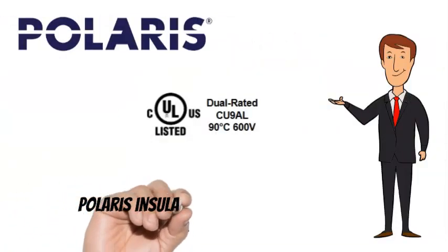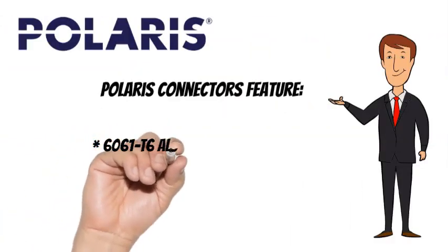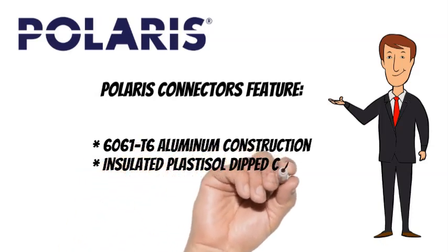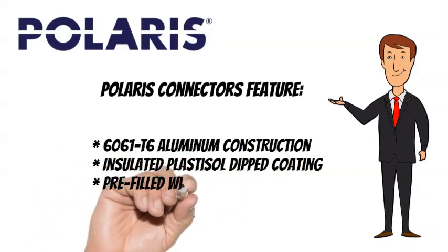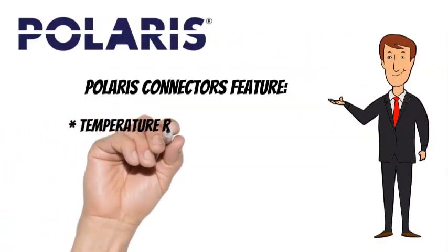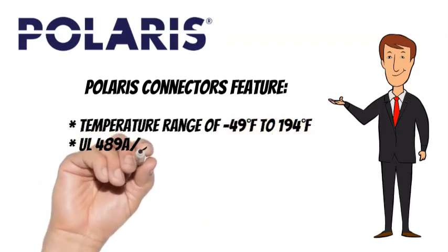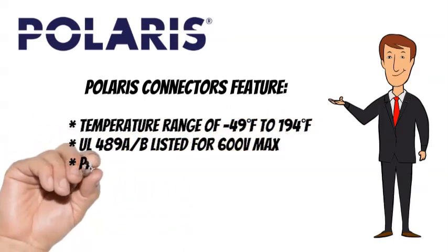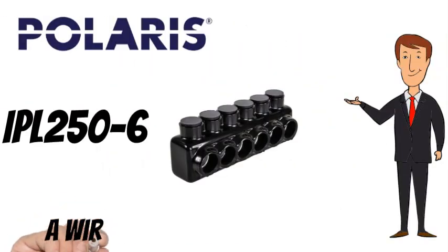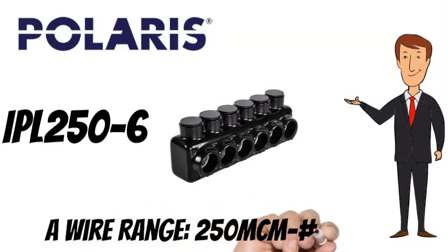Polaris taps are CULUS listed and also feature 6061-T6 aluminum construction, insulated plastisol dipped coating, and come pre-filled with oxide inhibitor. They have a temperature range of minus 49 degrees Fahrenheit to 194 degrees Fahrenheit, are UL489A/B listed for 600 volts max, and are parallel rated. The Polaris IPL250-6 has a wire range of 250 MCM to number 6 AWG.